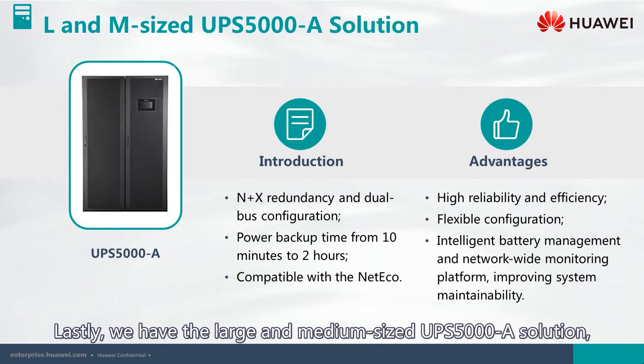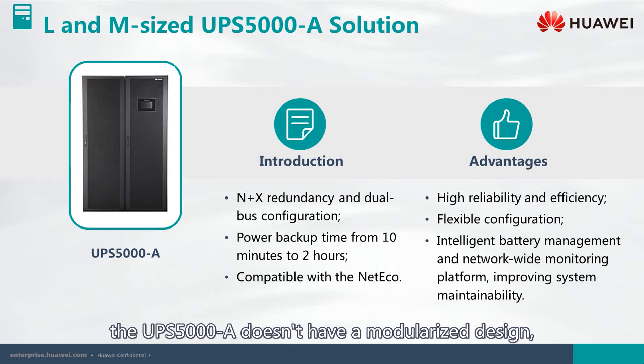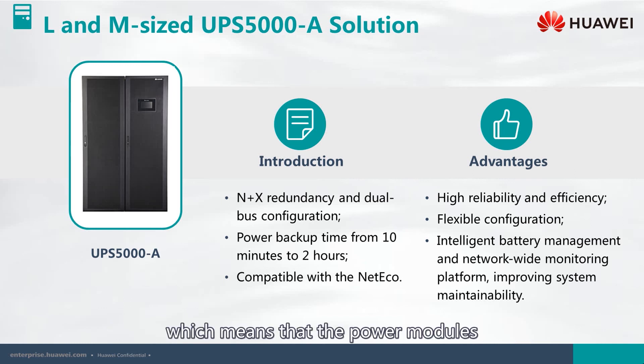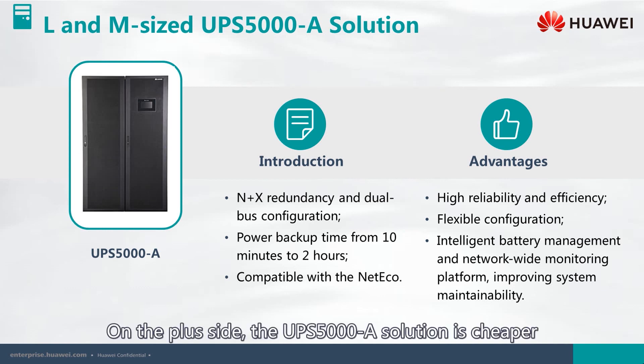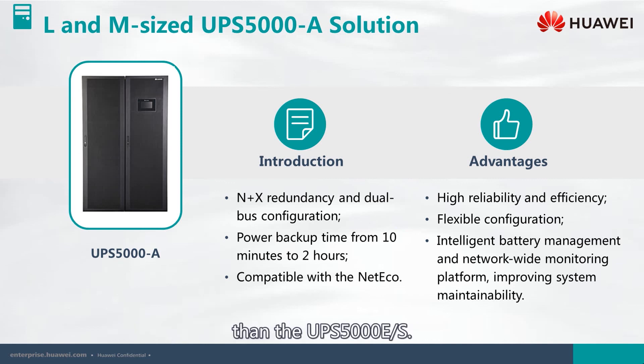Lastly, the large and medium-sized UPS 5000-A solution looks similar to the UPS 5000-E series, but the difference is that the UPS 5000-A doesn't have a modularized design, meaning the power modules are not independent from each other and cannot be replaced online like the UPS 5000-E or S. On the plus side, the UPS 5000-A is cheaper than the UPS 5000-E or S.